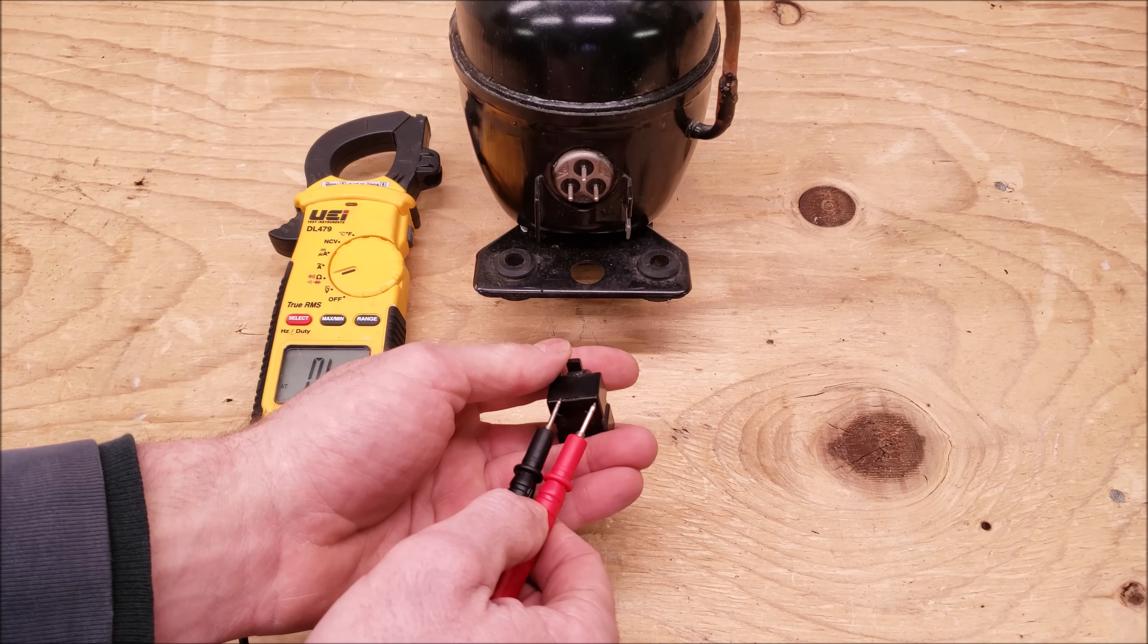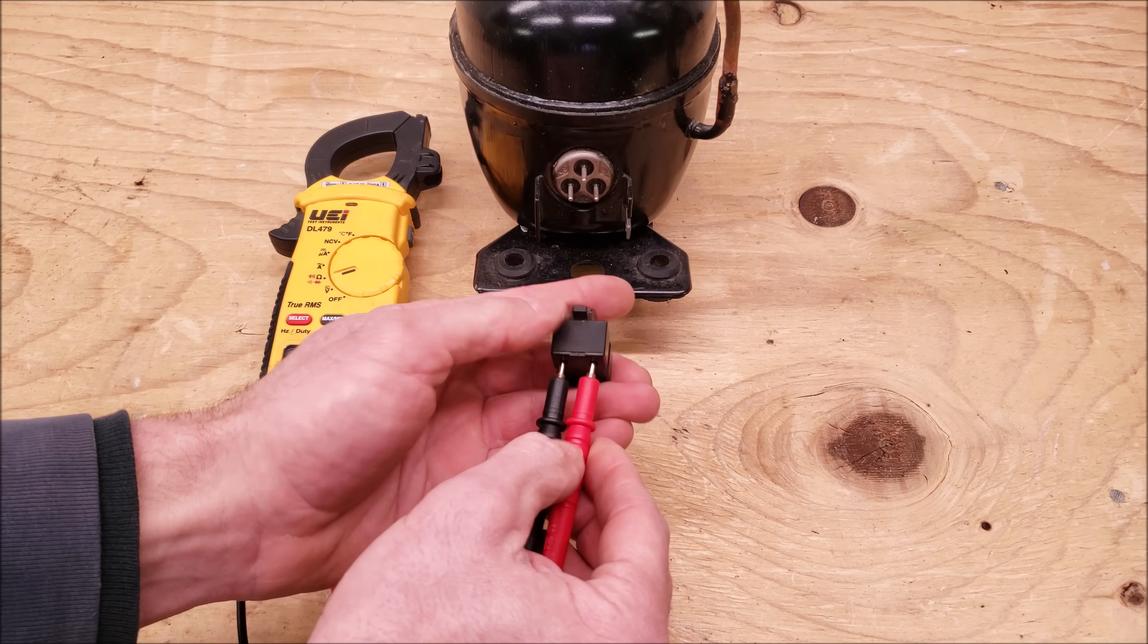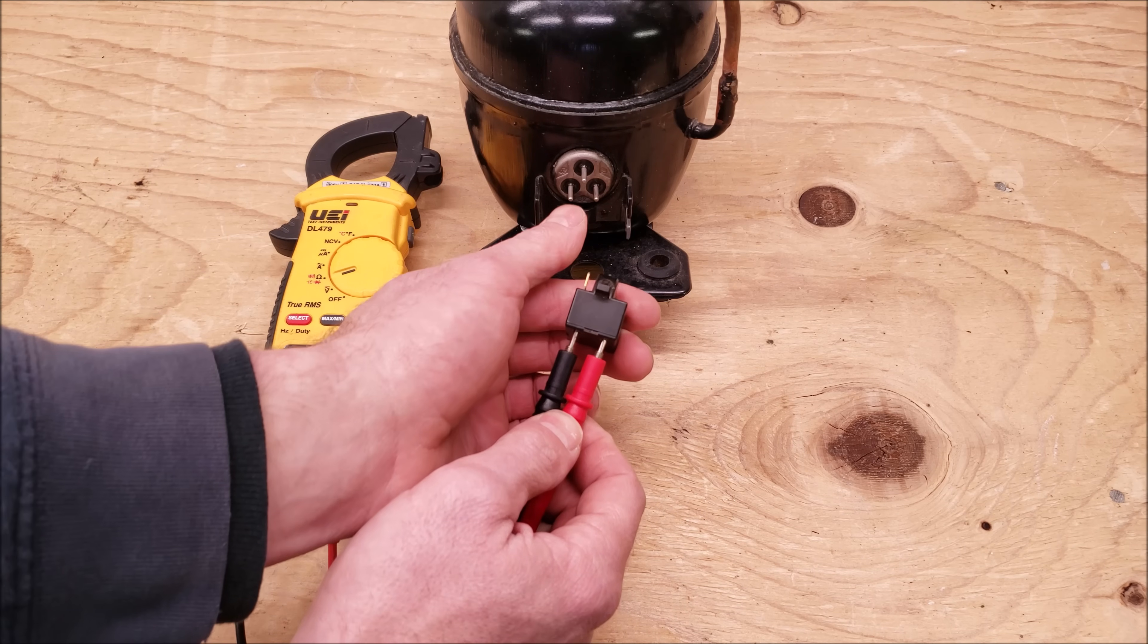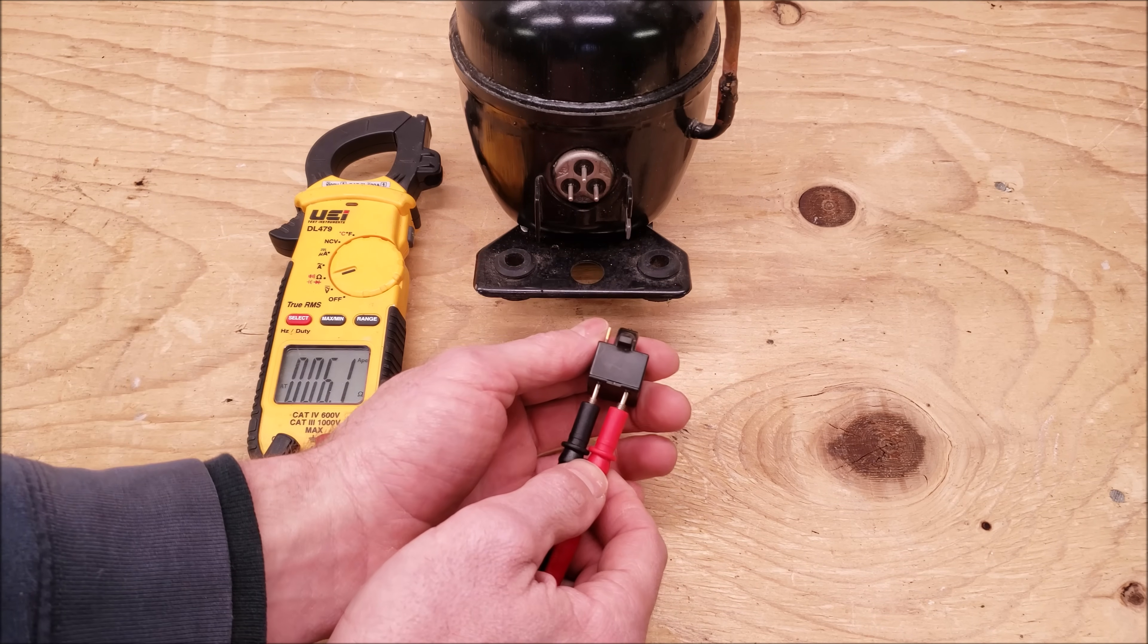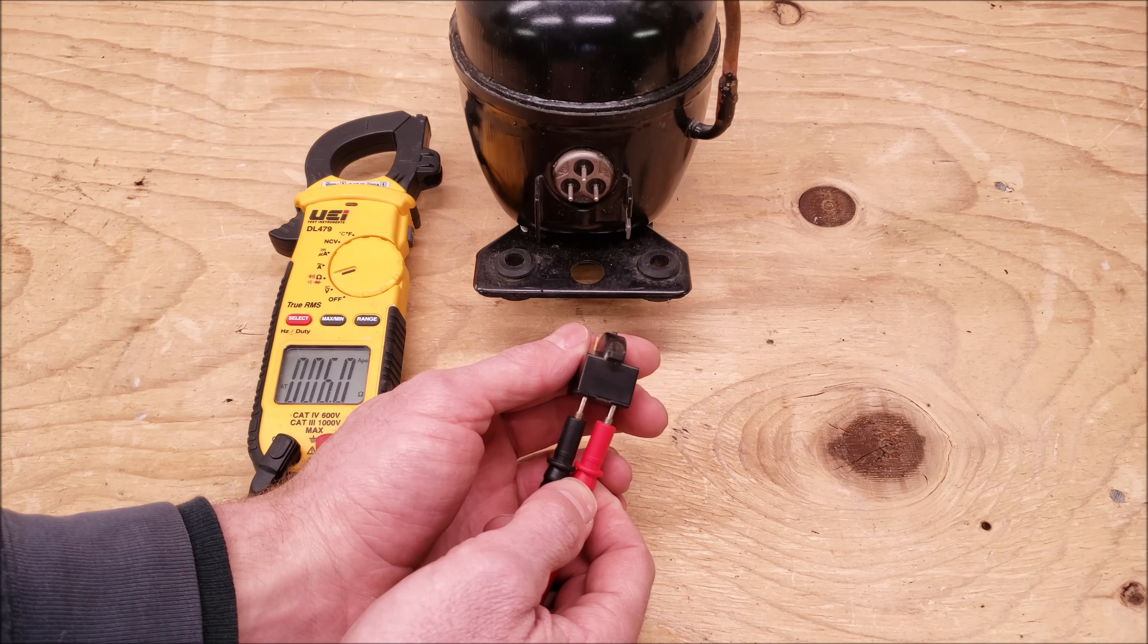So right here we have the multimeter set on resistance and we're going to go ahead and check inside these taps right here which connect the start winding to the run winding. And you see that we're reading six ohms of resistance.